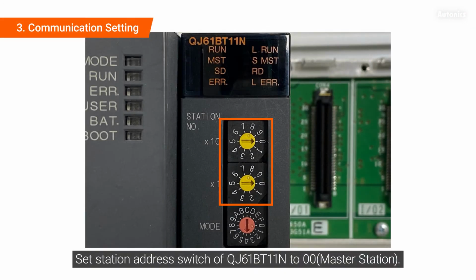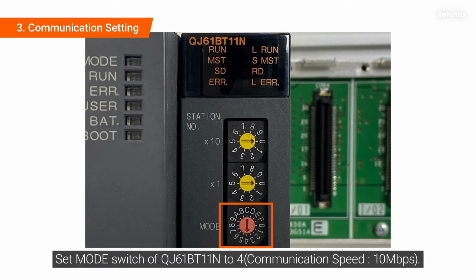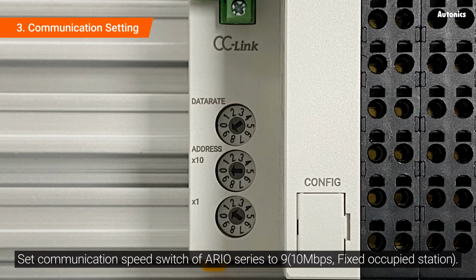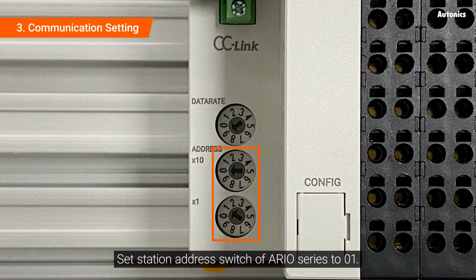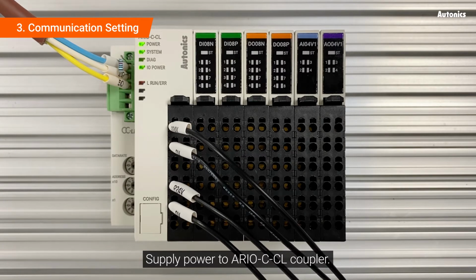Set station address switch of QJ61BT11N to 0. Set mode switch of QJ61BT11N to 4. Set communication speed switch of ARIO series to 9. Set station address switch of ARIO series to 1. Supply power to ARIO-C-CL coupler.